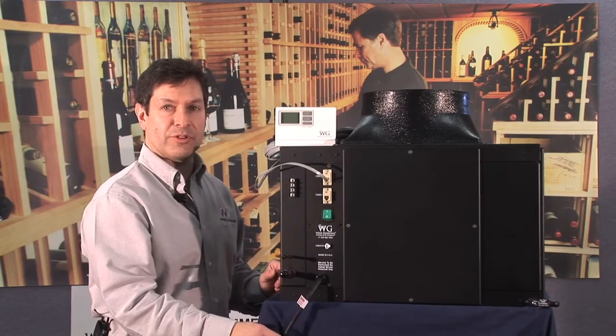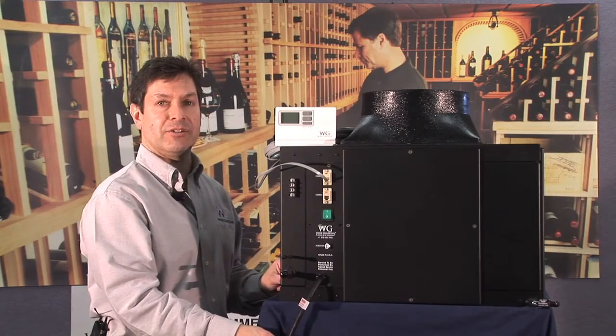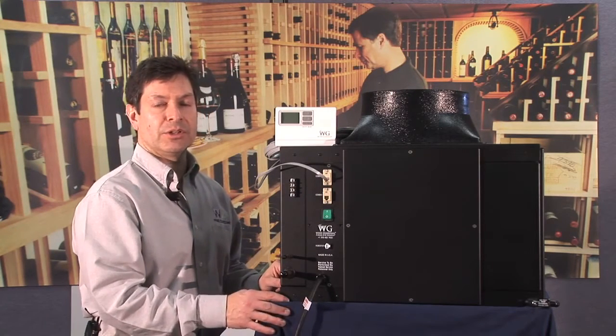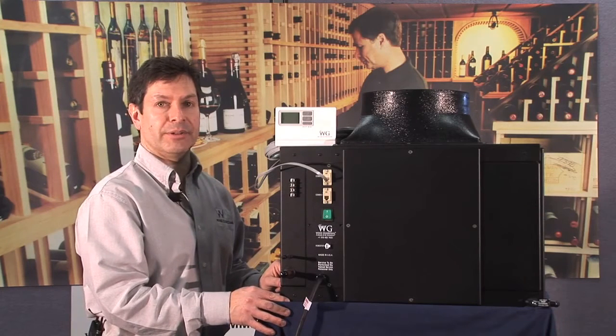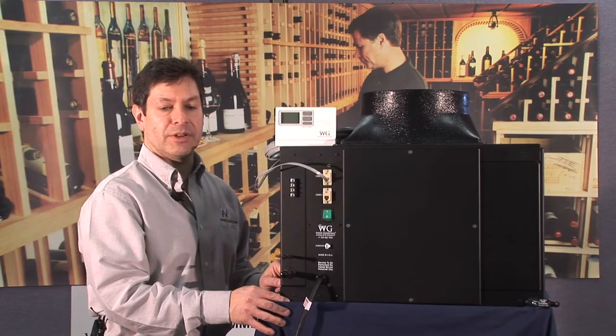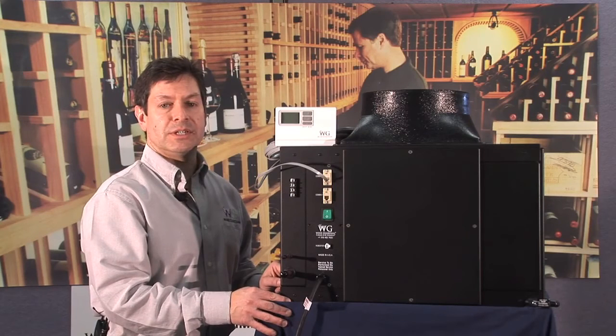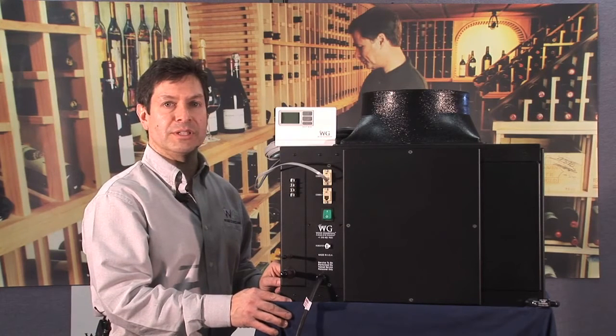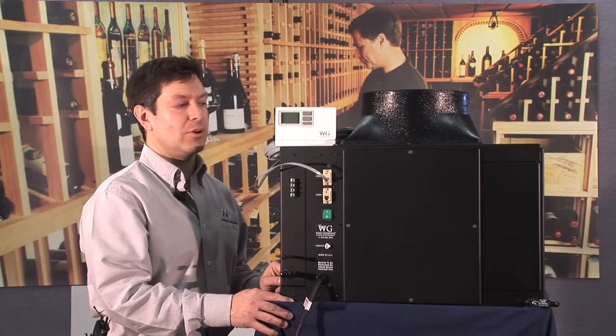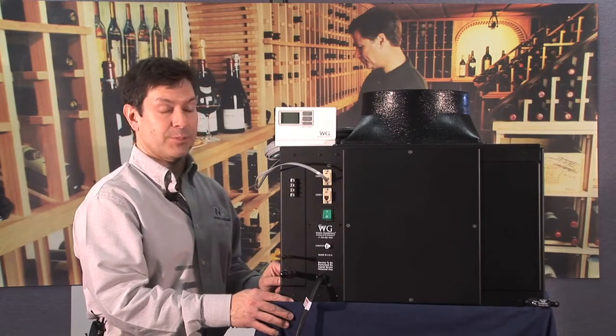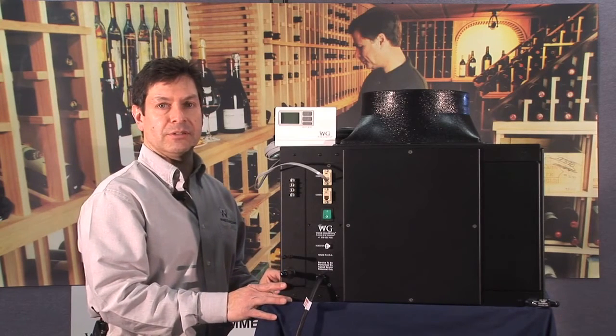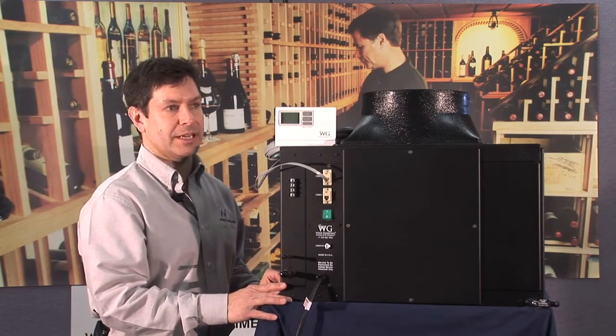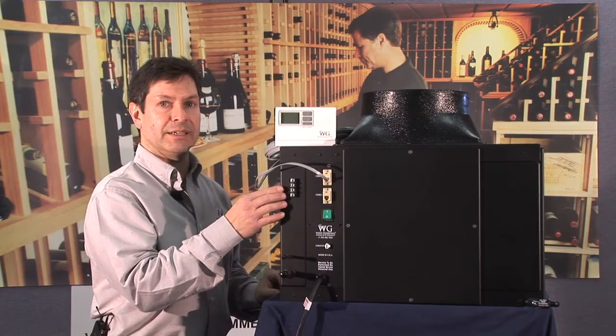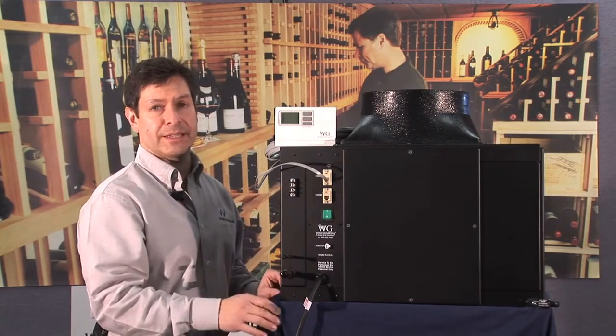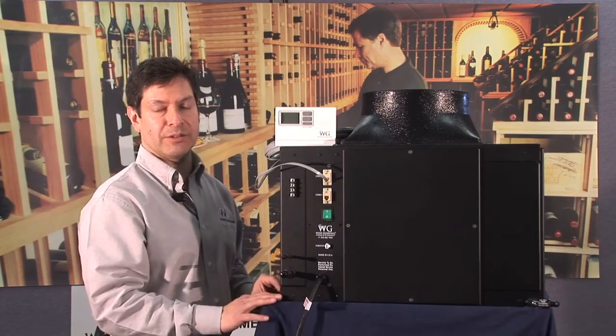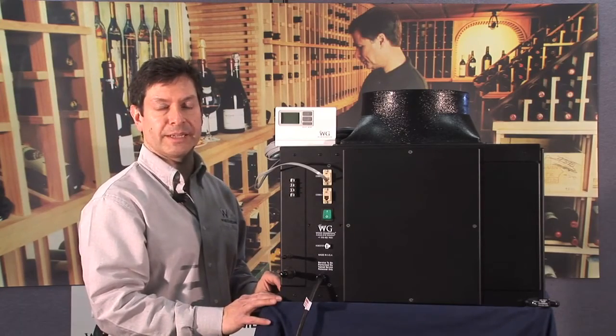I want to point out that power is required for the fan coil section in itself, and we'll also need power to the condensing unit. Typically, you'll have to follow local codes, but it is primary power with a disconnect switch. We also offer a contactor as part of this package, which helps make the connection between the 24 volt supply supplied at the fan coil and the condensing unit itself. That comes complete with our split system package.